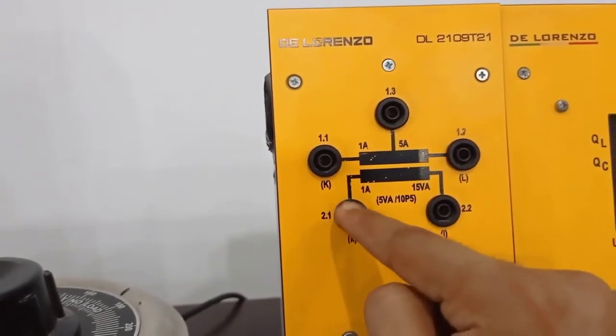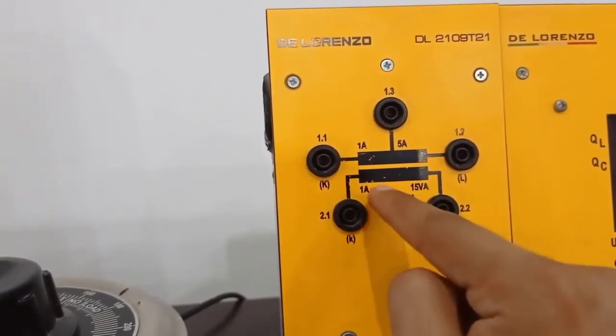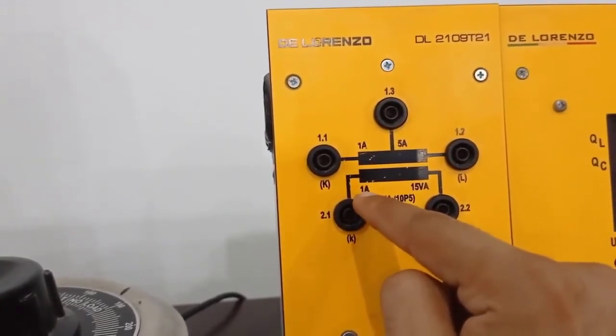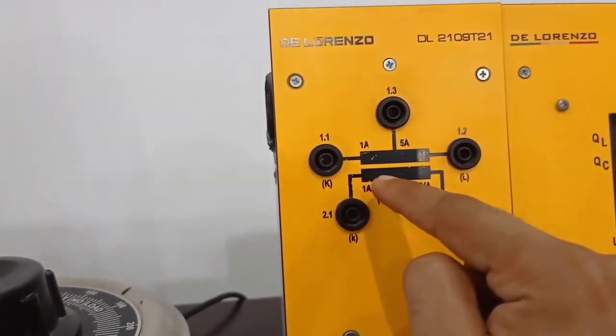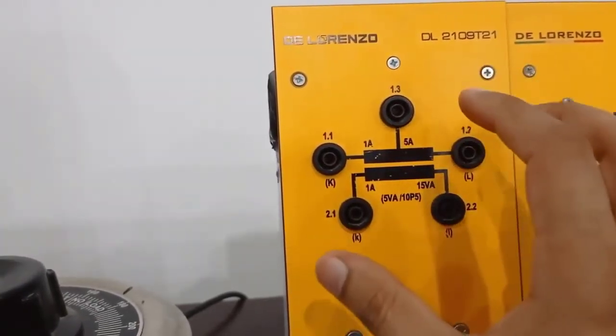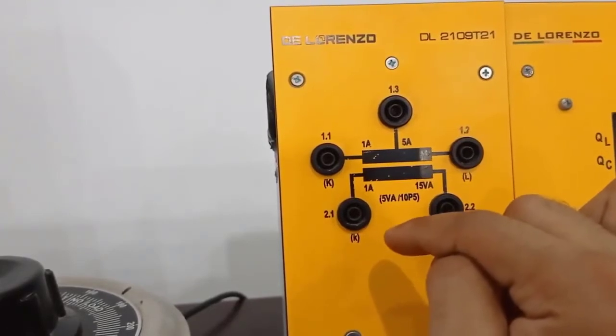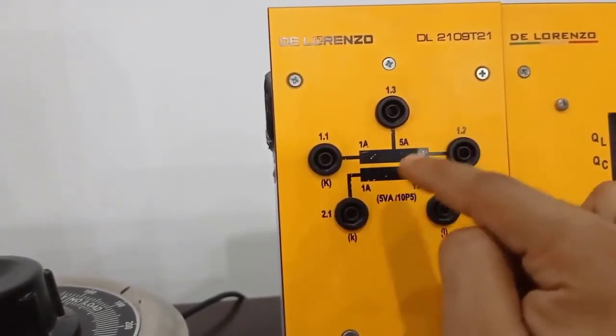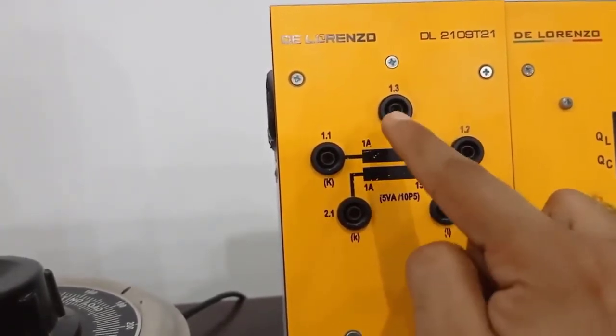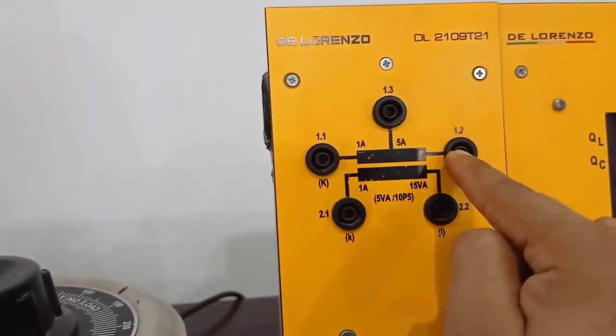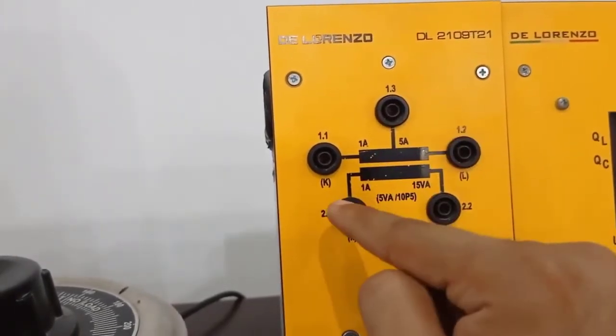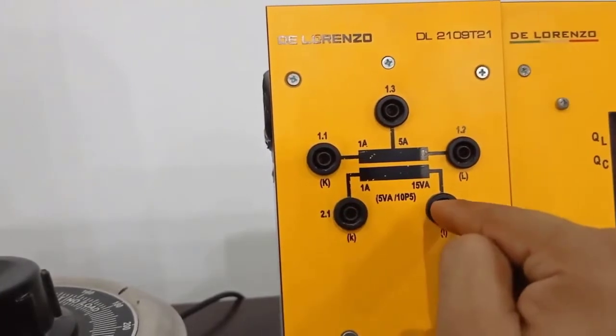On the secondary side we have only one rating available. Secondary is rated at 1 ampere. According to the instruction given in the manual, we will use this CT in the configuration of 5:1 ratio. That means primary rated at 5 ampere, secondary rated at 1 ampere. So the primary will be connected between these two points, and the secondary circuit will be connected at these two points.